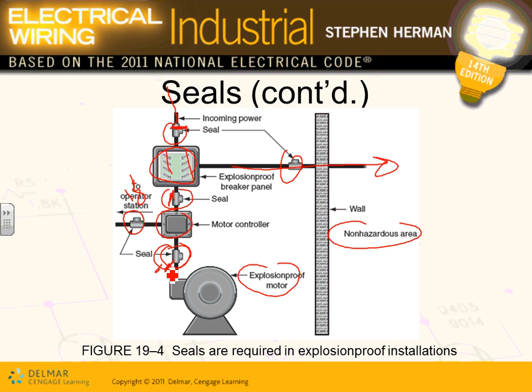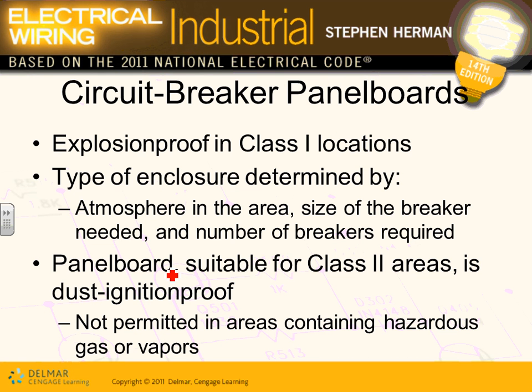Any questions about sealing? So sealing, you have to seal around arcing and sparking equipment like panels and circuit breakers and motors and what not. Every time you exit, you have to seal within 18 inches of every piece of equipment that arcs and sparks. Any comments, any questions? Seal is a big deal. You're going to see a couple of things later on, guys, about sealing.